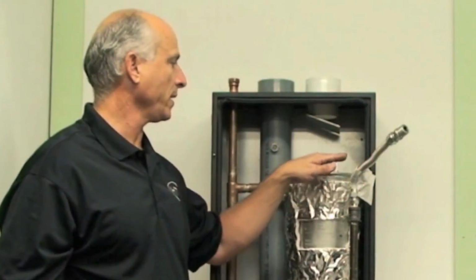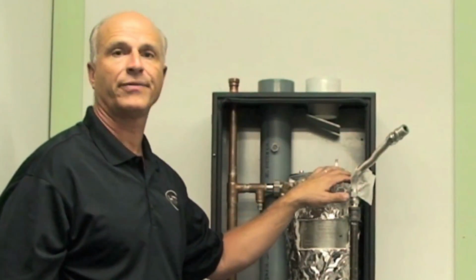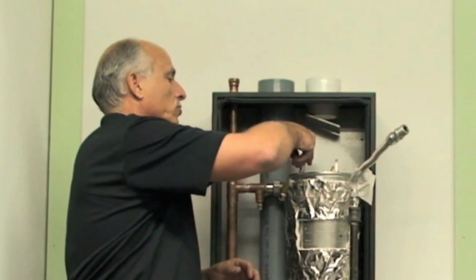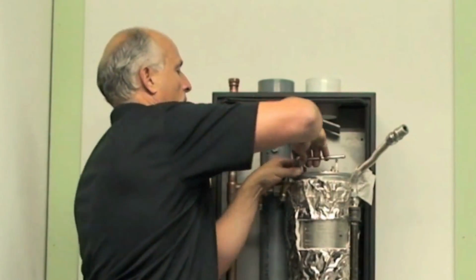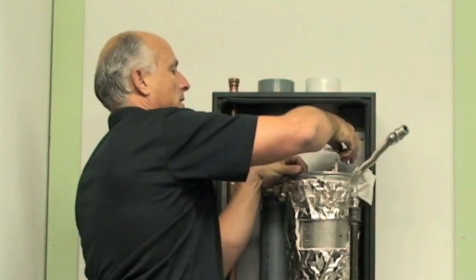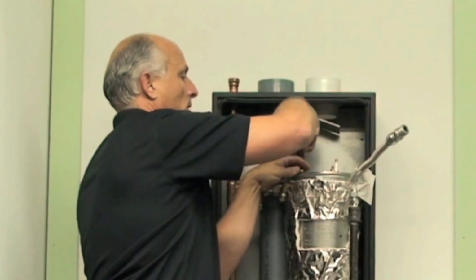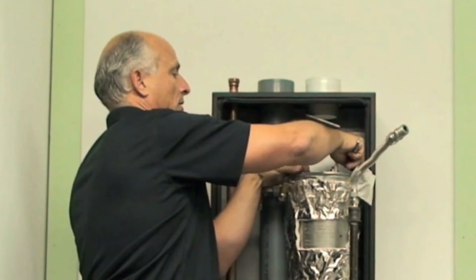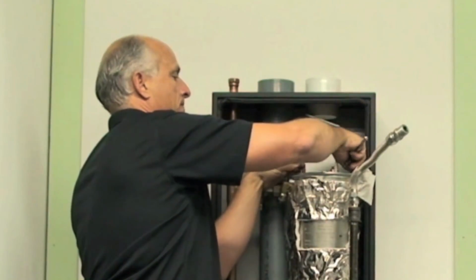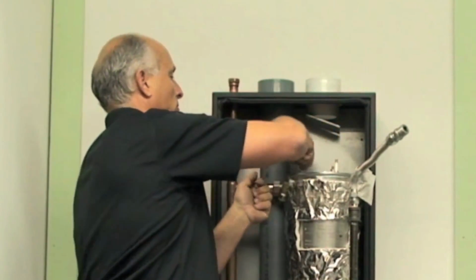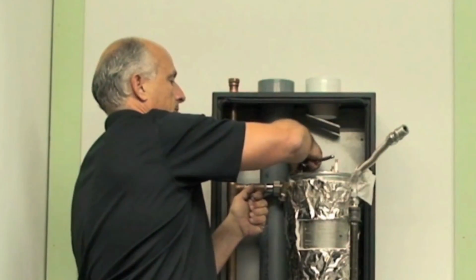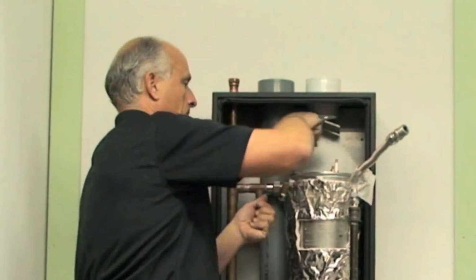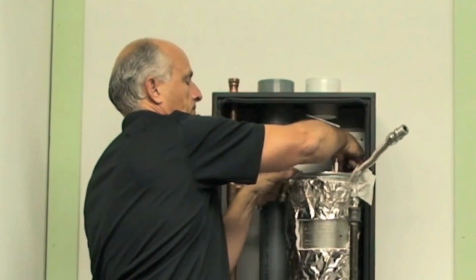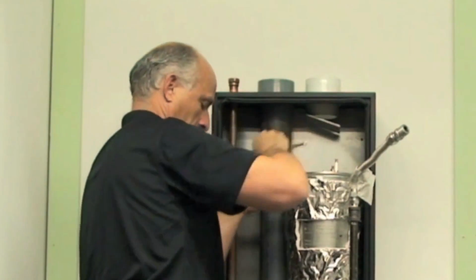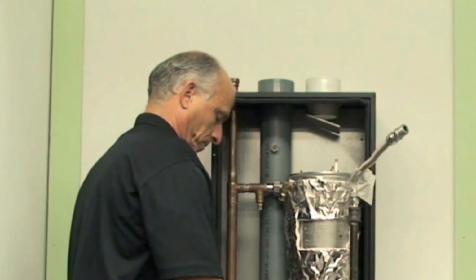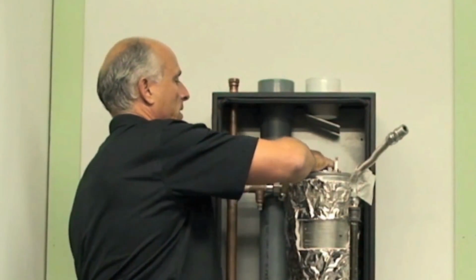What I'm going to do is I'm going to take the burner mounting plate off. You need a 10mm screwdriver or a ratchet. You're going to disconnect it. Disconnected all these here. There's 4 located on the boiler. Again, there's plenty of clearance to get to them. These are very similar to the ones we have on our other boilers, the Elite. Plate out.